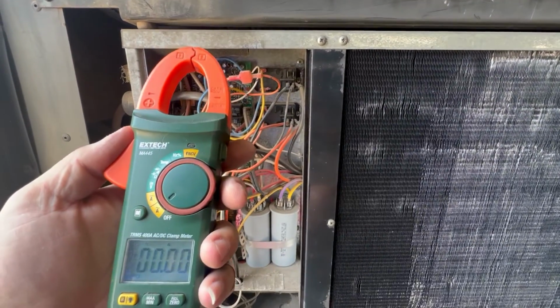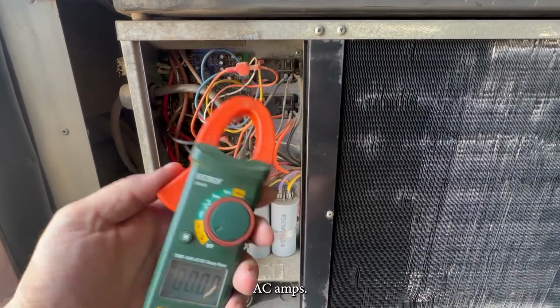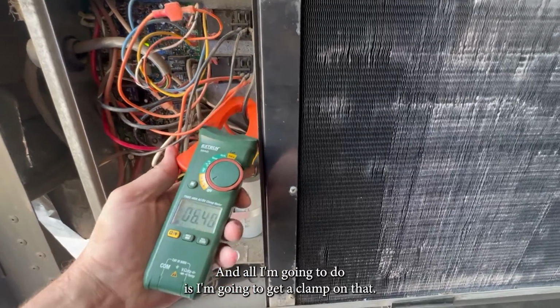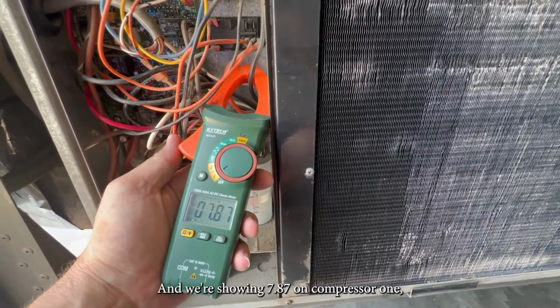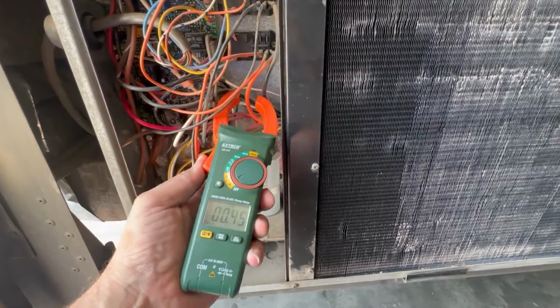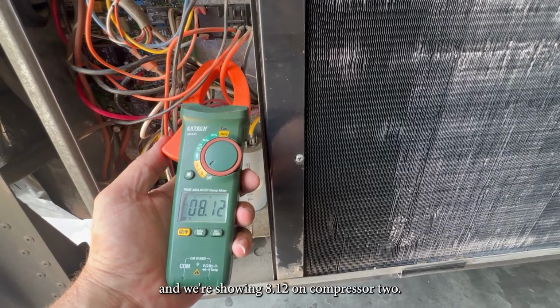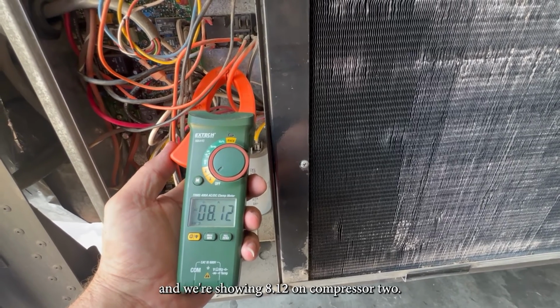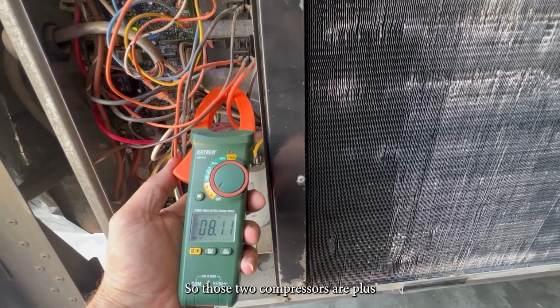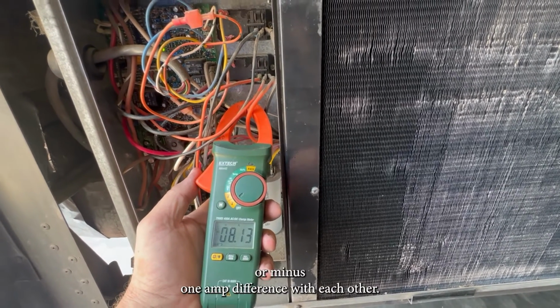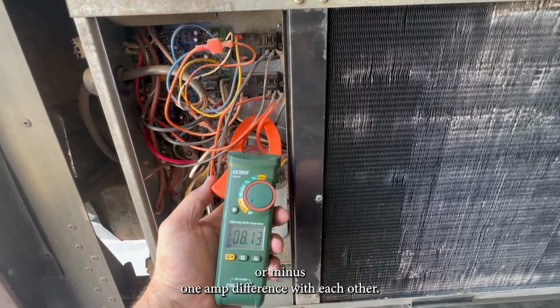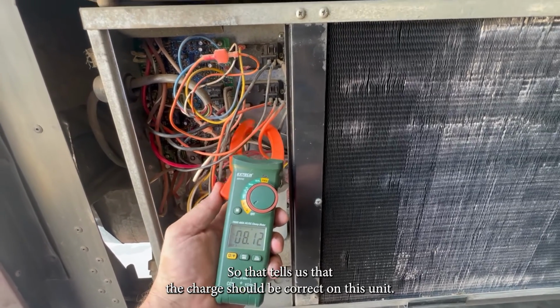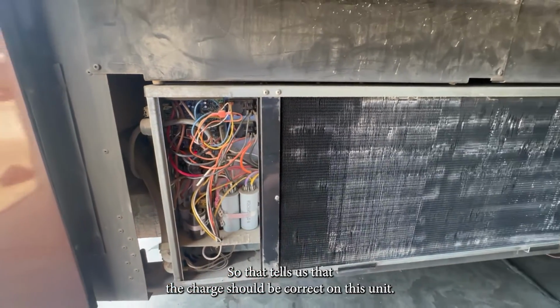So what we're going to do now is take our clamp-on meter here and set it on AC amps, and all I'm going to do is get a clamp on that. We're showing 7.87 on compressor 1 and we're showing 8.12 on compressor 2. So those two compressors are plus or minus 1 amp difference of each other. So that tells us that the charge should be correct on this unit.